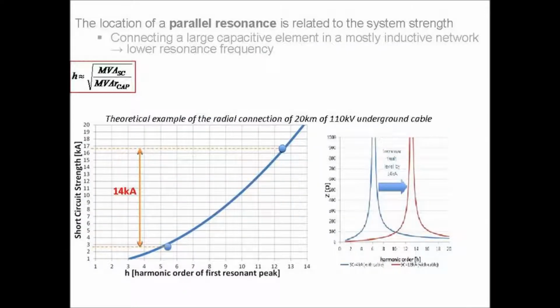So I suppose just talking about system strength, I do have another equation here. This one's fairly straightforward. It's the root of the short circuit MVA over the megavar capacitor bank. So that will give you a rough idea of where your first harmonic resonance is going to occur. So normally the network is fairly inductive. We've got fairly long 110 kV or 220 or 400 kV overhead lines, which tend to have resonances higher up the scale. But when you connect capacitive elements, so something like an underground cable or new capacitor bank or whatever it is, that will lower that resonance frequency. So you want to shift it back up the scale. The higher up the scale it is, the better. It's further away from any kind of device's resonances.